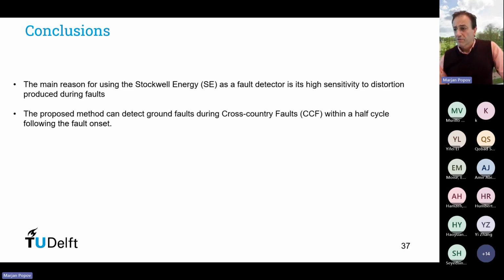The main conclusion of this work is that the main reason for using the Stockwell energy as a fault detector is its high sensitivity to distortion produced during fault currents. And the proposed method can detect ground faults during cross-country faults within a half cycle following the fault onset.